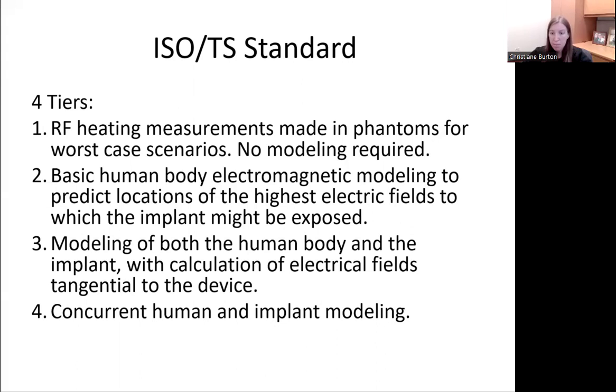3. Modeling of both the human body and the implant with calculation of electrical fields tangential to the device. And 4. Concurrent human and implant modeling. Tier 3 is required for larger and more complex devices, while Tier 4 is only infrequently performed due to its complexity. All mathematical simulations must be verified by actual measurements in a tissue mimicking phantom similar to that pictured in my last slide.